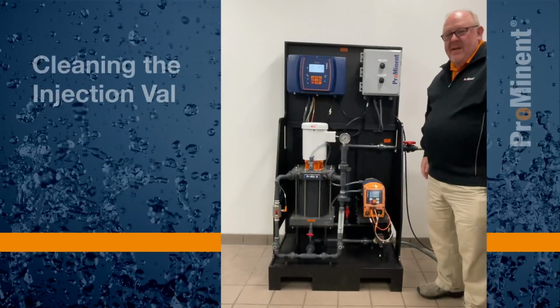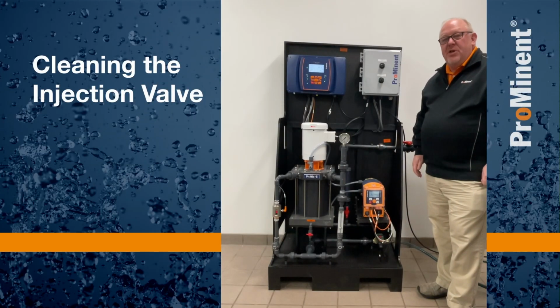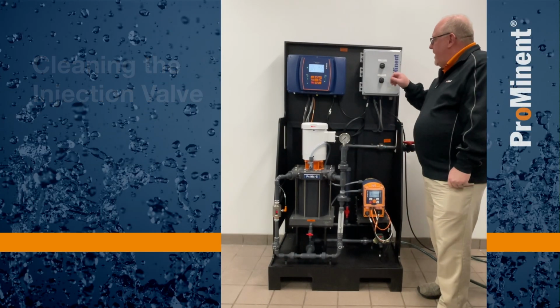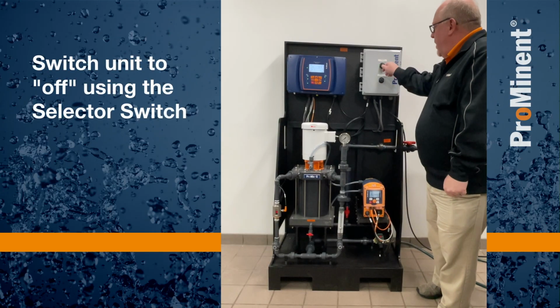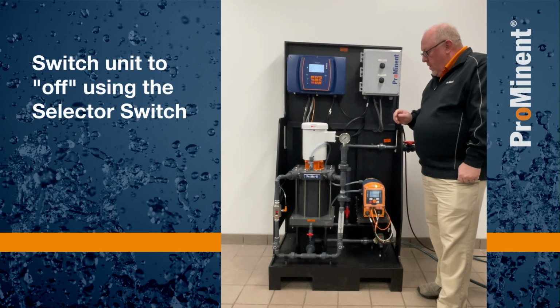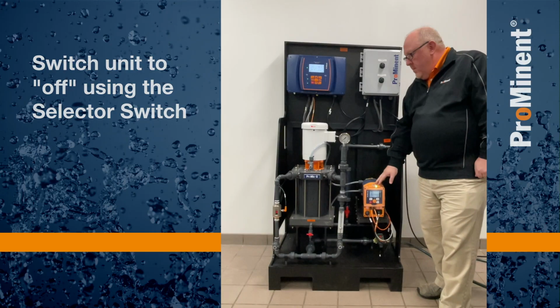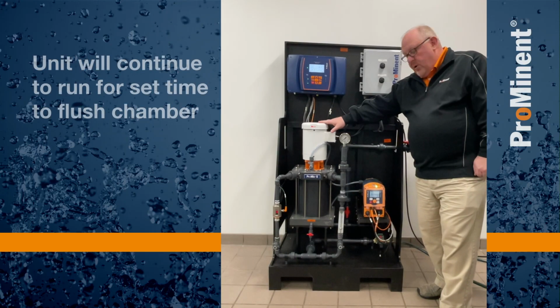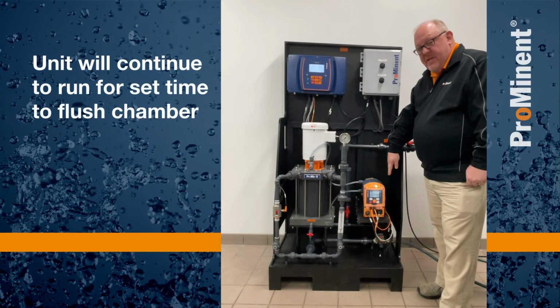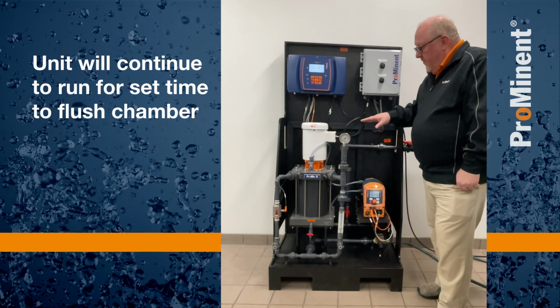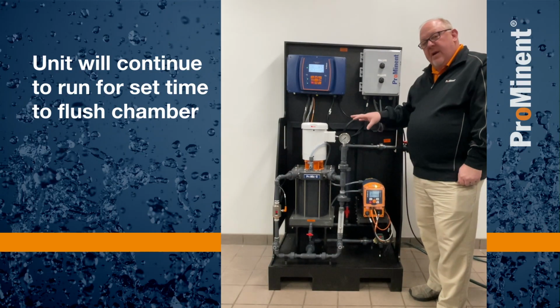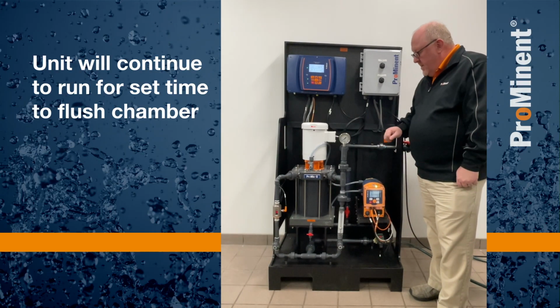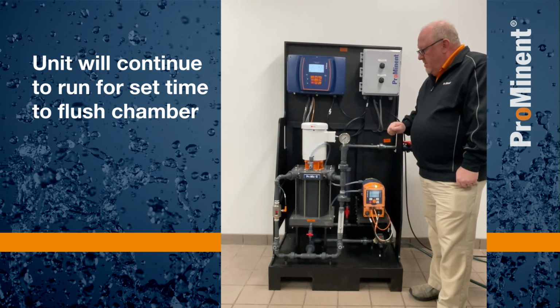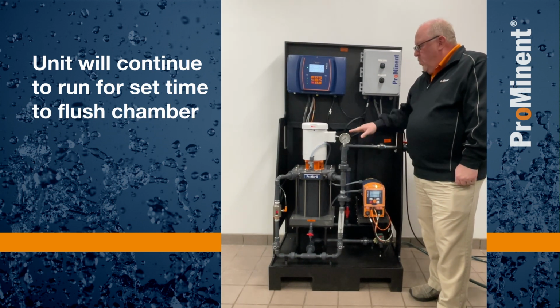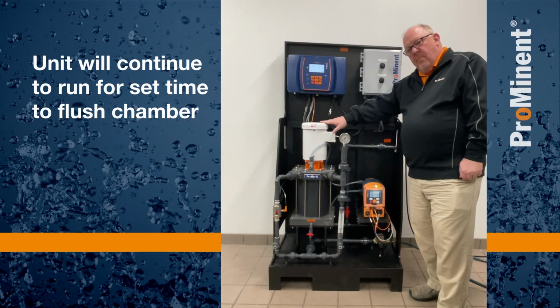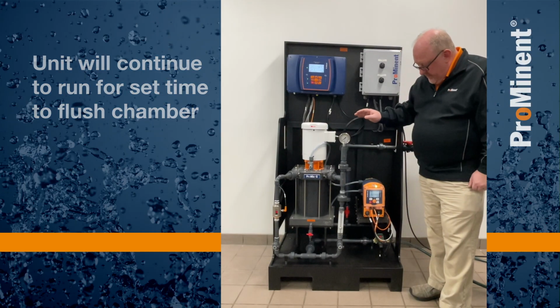Okay, at this time, we'd like to show you the maintenance on the injection valve. So we would like to stop the unit. We're going to use our switch to do that. Right now, the unit will stop pumping polymer. It's running a flush, so the motor is running, the water valve stays open. We have that running for our desired time. In our case, we're at the default of 30 seconds. We wait for that to finish. Once that finishes, we'll know because the motor will stop as well. So we'll let that finish up.